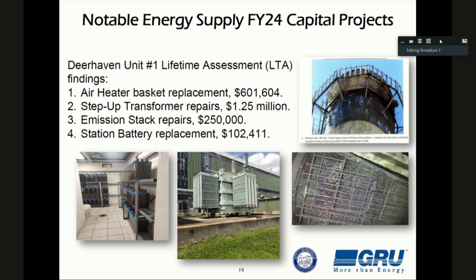For the generator on Deerhaven 1, there are 2 step-up transformers. Both those transformers are 50 years old, just like the unit was. So for us to extend those transformers beyond that 50 years, there's a scope of work we had to develop, working with our partners in energy delivery. Part of that is radiators, part is insulators and bushings, part is internal inspections in transformers. Our estimate is about $1.25 million to upgrade those transformers to get us through 2027 reliably.